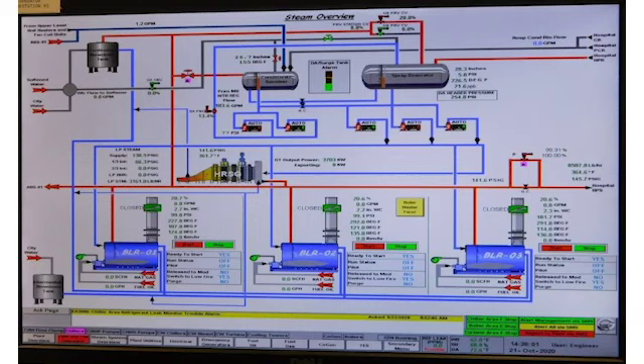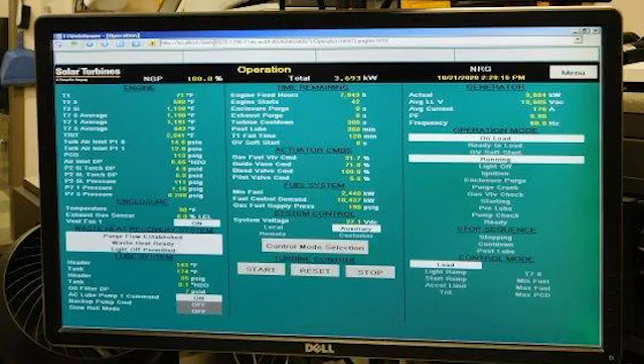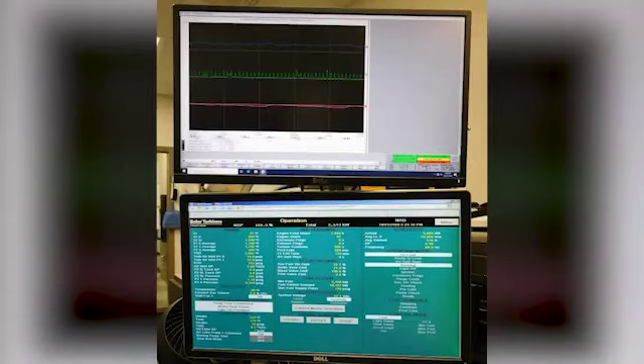Here, a lot of this is being communicated again just through a Modbus interface into the main plant PLC and being rebroadcasted here on the screen. And we have some of it dispatchable, some of it being view only. We have the cogen HMI here. This is the solar HMI and plant trending. We use the trending quite a bit actually to identify and troubleshoot issues that are occurring in the plant.